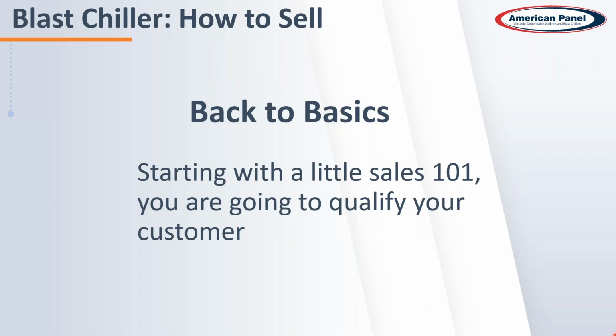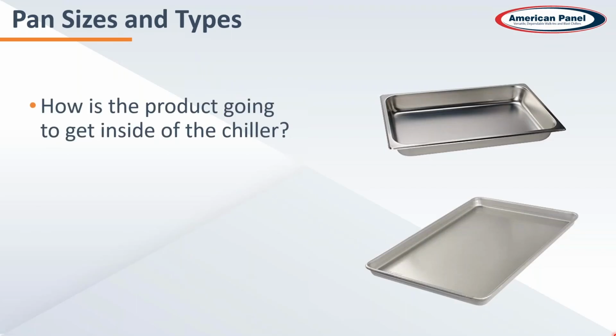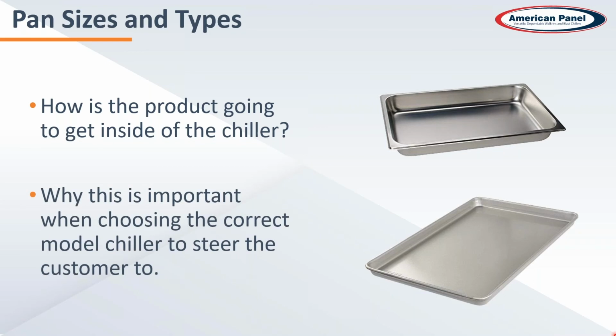With a blast chiller, a very important starting point is going to be pan sizes. One of the main ways that our units are sized and designated is based on the pan size. So you talk about the food service pans, you talk about how is the hot product going to get inside that blast chiller? Is it going to be steam table pans? Is it going to be sheet pans? Is it going to be fractional pans? All of that's important to know so you can direct the customer in the right direction. It's important because different blast chillers have different size compartments, and you don't want to get the customer who's happy about their new $20,000 appliance and firing it up and then not be able to fit their pans into the unit.